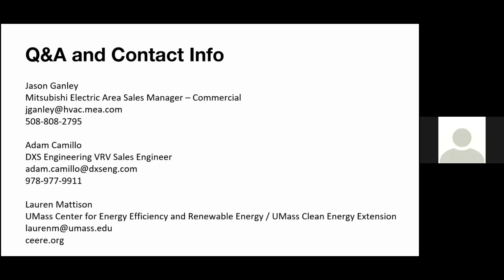I just want to address Robert Zog's question there, asking why a cooling tower is needed for the water source heat pump option with the cold canal water available to reject heat. I think that they didn't want to look into that whole infrastructure of providing the heat exchanger for that canal. I think there's all sorts of different ratings for those heat exchangers, which would add quite a bit of cost. So I think they were just looking at using a cooling tower instead.